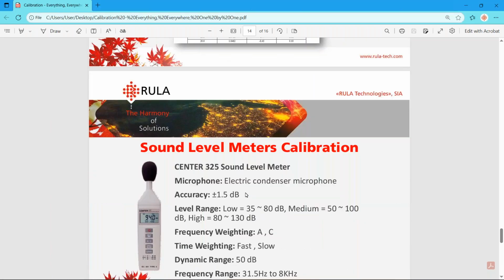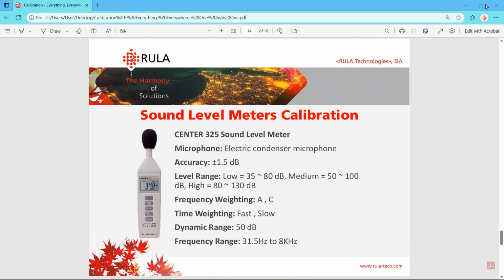And I would like to open the presentation to tell you a few technical characteristics of the sound level meter we have. So it is Center 325. And it has an electric condenser microphone. Its accuracy is plus minus 1.5 decibel. The level ranges in which the sound level meter works: the sound level meter has 3 level ranges: low, medium, and high. Frequency ratings are A and C. Time ratings are fast and slow. The dynamic range of the sound level meter is 50 decibel, and the frequency range is from 31.5 hertz up to 8 kilohertz.